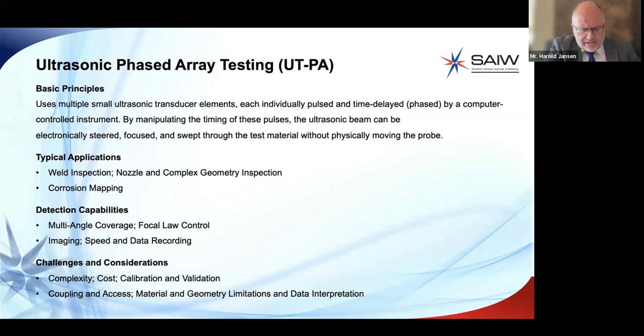Some of the challenges that need to be considered: the complexity of the instrument itself. So in other words, the instrument setup, focal law calculation, and scan plan development require highly trained personnel, whereas the incorrect setup can result in missed or mischaracterized indications.